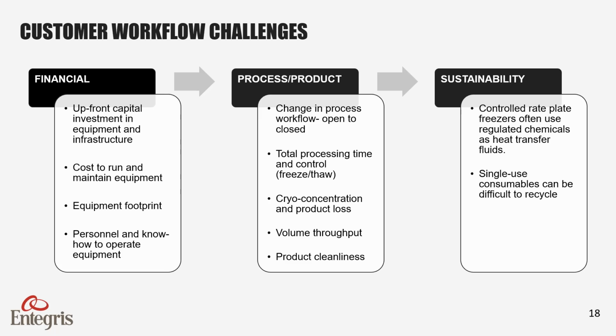The top financial challenges include upfront capital investment. Controlled rate freezers can cost over $1 million, not including the infrastructure, which may include a chiller for water cooling the compressor, the electrical hookups, the floor space costs, and so on, to house and operate this equipment. Coupled with the investment is the concern that the equipment will not meet the process needs. When that happens, users often change the process to best fit the equipment. The cost to maintain this equipment is also pretty high, with specialized freeze and thaw equipment. Reliability and uses other than the design intent further reduce the reliability, causing unplanned downtime in the manufacturing process.